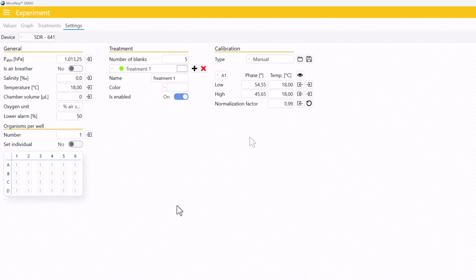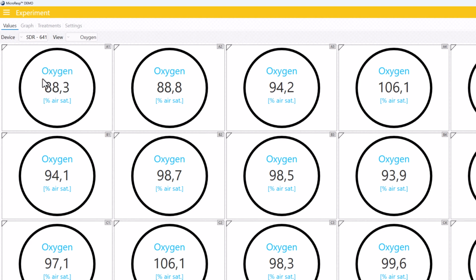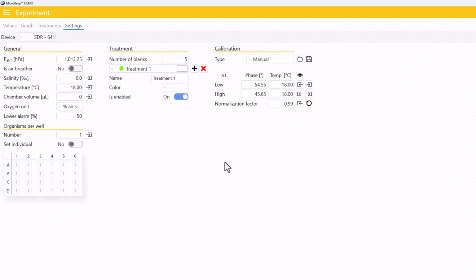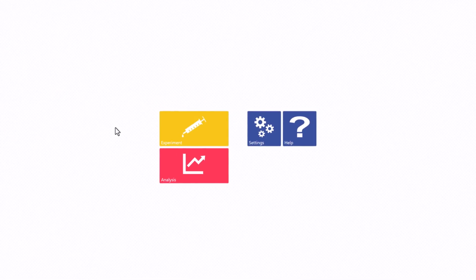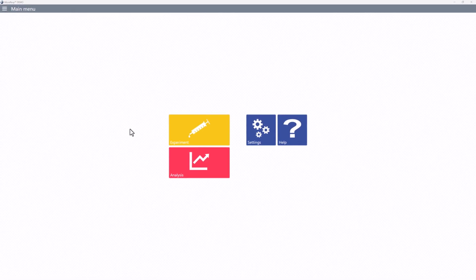We generally recommend performing a new calibration if the experimental temperature differs more than plus minus 1.5 degrees of the current calibration temperature, if the air saturation readings start to vary by more than plus minus 10%, or after performing a sterilization using ethanol according to the quick guide. And that's it on how to calibrate your oxygen sensors in MicroResp.